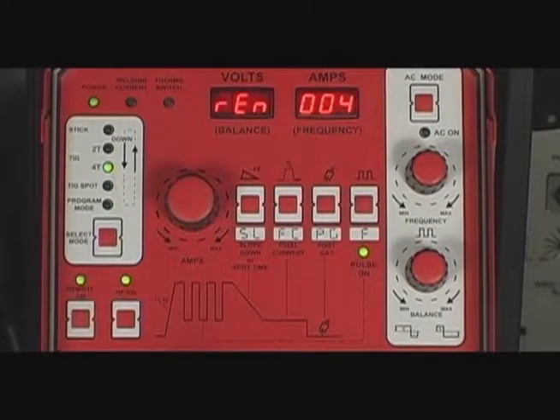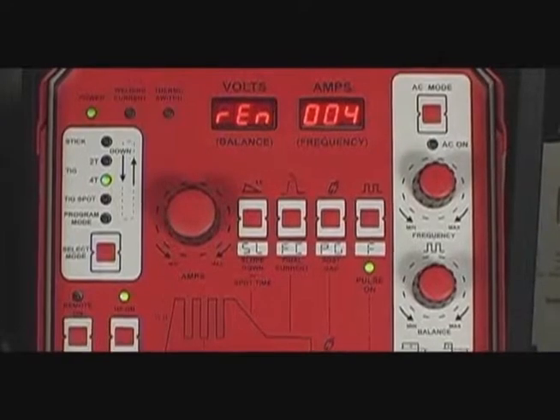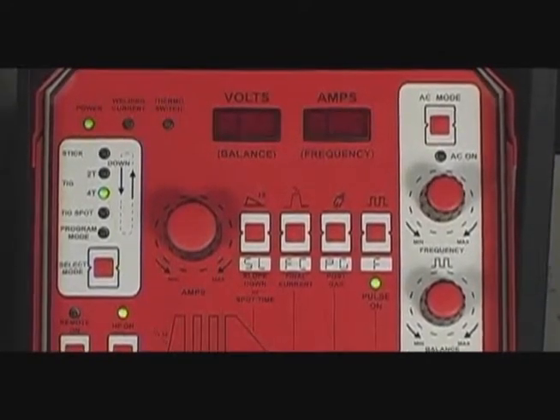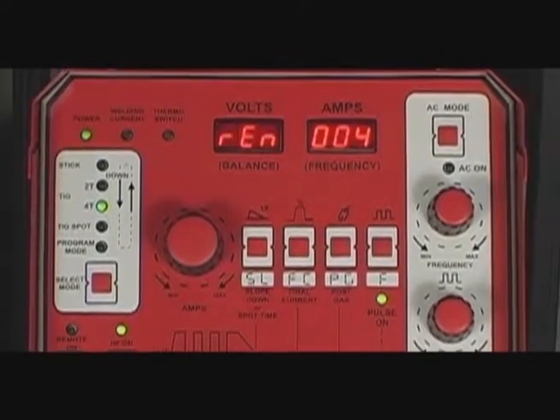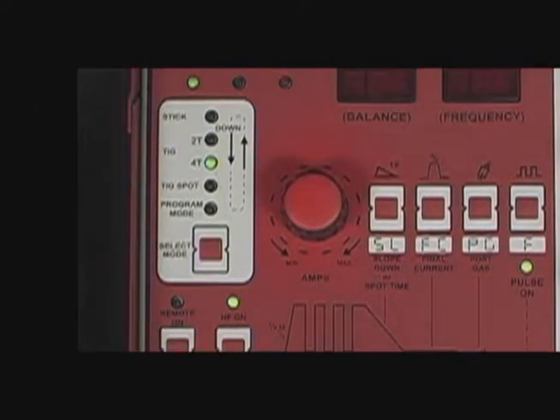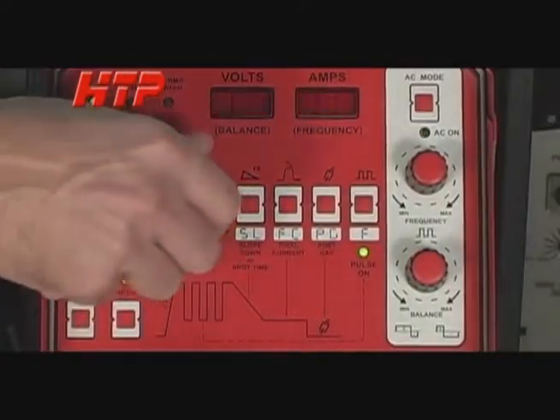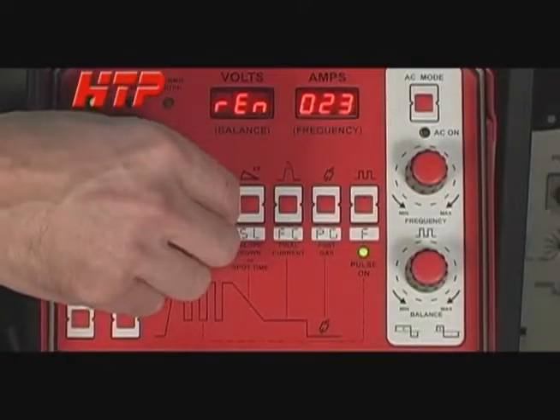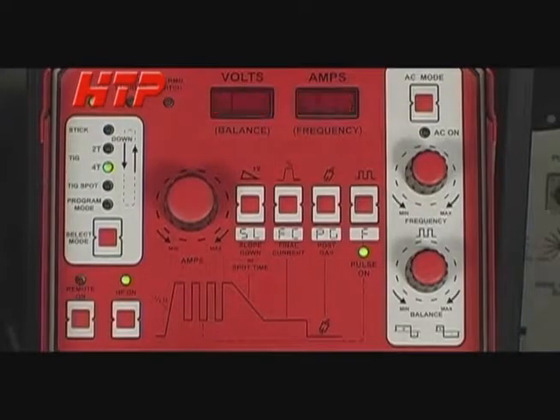If you wanted to start at a higher amperage, push the remote on button. REM is flashing and displayed in the volts display, and the starting amperage is flashing and displayed in the amps display. While both displays are flashing, adjust the amperage adjustment knob to adjust the starting amperage to the desired setting. I will adjust the starting amperage from 4 amps to 25 amps.